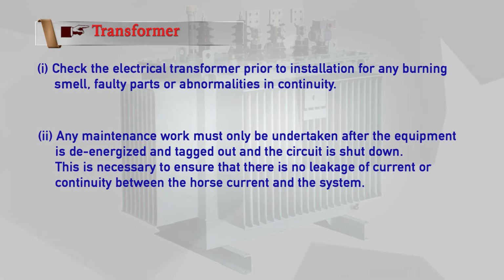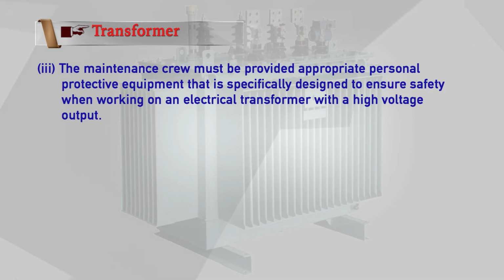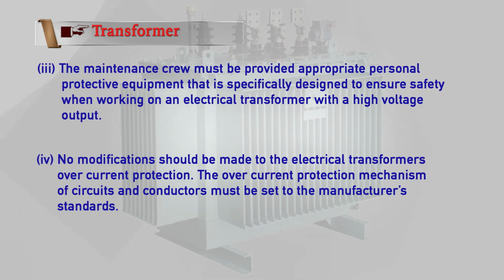the system. Third, the maintenance crew must be provided appropriate personal protective equipment that is specifically designed to ensure safety when working on an electrical transformer with a high voltage output. No modifications should be made to the electrical transformer overcurrent protection. The overcurrent protection mechanism of the circuit and conductor must be set to the manufacturer's standards.